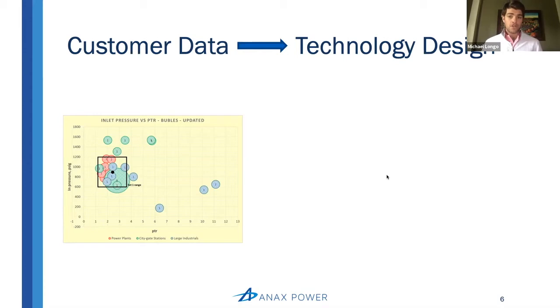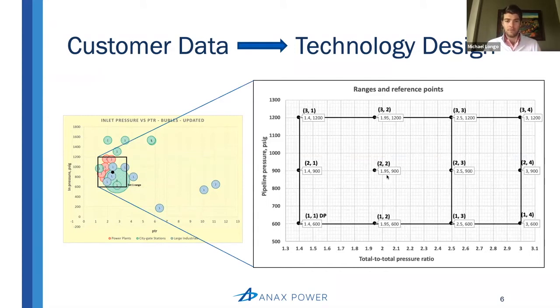We literally drew a rectangle around the market that we wanted to serve, where the majority of our customer gas conditions resided, and said, let's design technology capable of serving this part of the market with a single design. The result were these 12 design points that make up this rectangle. The key takeaway is that anywhere within this rectangle — anywhere from 600 PSI to 1200 PSI on the inlet side and from a pressure ratio of 1.4 to 3.0 — Anax is going to be able to generate full 500 kW capacity at very high efficiency. This makes up the majority of our customer market, and our technology is capable of serving it with just a single design, which is a game changer.